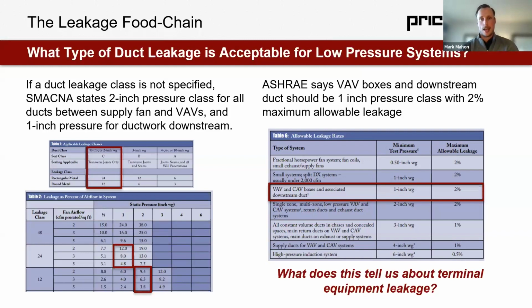Now, what does ASHRAE say? Well, ASHRAE says VAV boxes and downstream ductwork should be a 1-inch pressure class if it's tested, but at a minimum a 1-inch pressure class with 2% maximum allowable leakage. So this is exceeding the requirements from SMACNA. This comes from the ASHRAE handbook. It comes from ASHRAE 90.1.